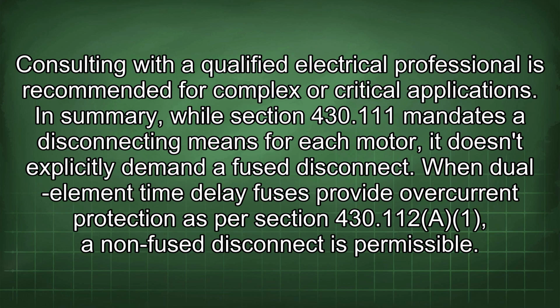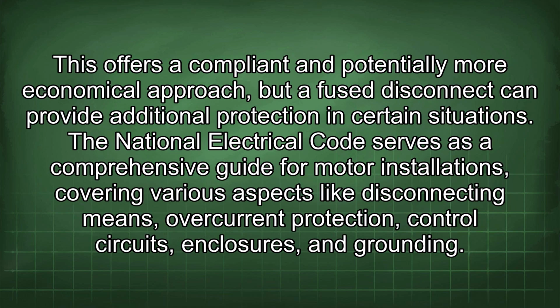In summary, while Section 430.111 mandates a disconnecting means for each motor, it doesn't explicitly demand a fuse disconnect. When dual-element time delay fuses provide overcurrent protection as per Section 430.112a, a non-fused disconnect is permissible. This offers a compliant and potentially more economical approach, but a fuse disconnect can provide additional protection in certain situations.